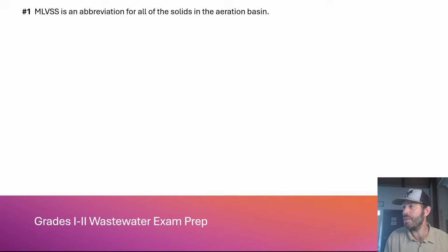MLVSS is an abbreviation for all solids in the aeration basin. This is false. MLSS is an abbreviation for all the solids in the aeration basin. MLVSS is volatile suspended solids, not all suspended solids, okay? MLVSS is volatile suspended solids, which is a direct biomass measurement. MLSS is everything, okay? So this would be false.